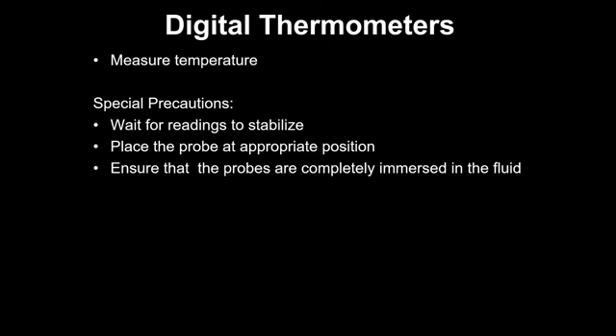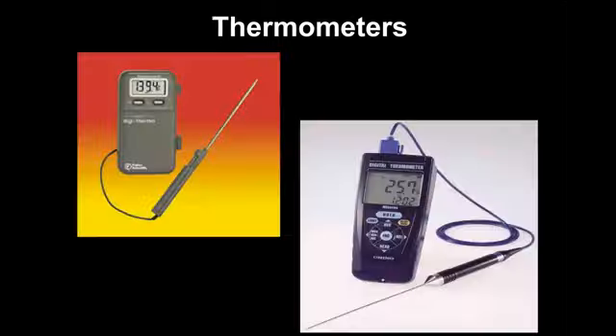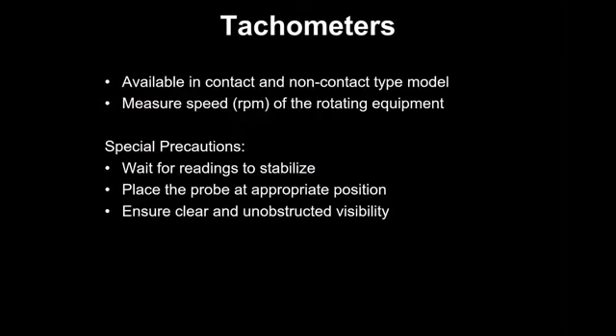These are thermometers. I don't have to say much about it. It is for measuring the temperature, waiting for the reading to stabilize, standard. Tachometers are for measuring the RPM. So they are available in contact and non-contact type. RPM measurement becomes critical, especially when you have belt-driven equipment. Of course, belts are getting outdated, but still, in some cases you have belt-driven equipment. Now, if the belt is loose, there can be slippage, and the extent of slippage needs to be measured. So for that, we need to have a measurement.